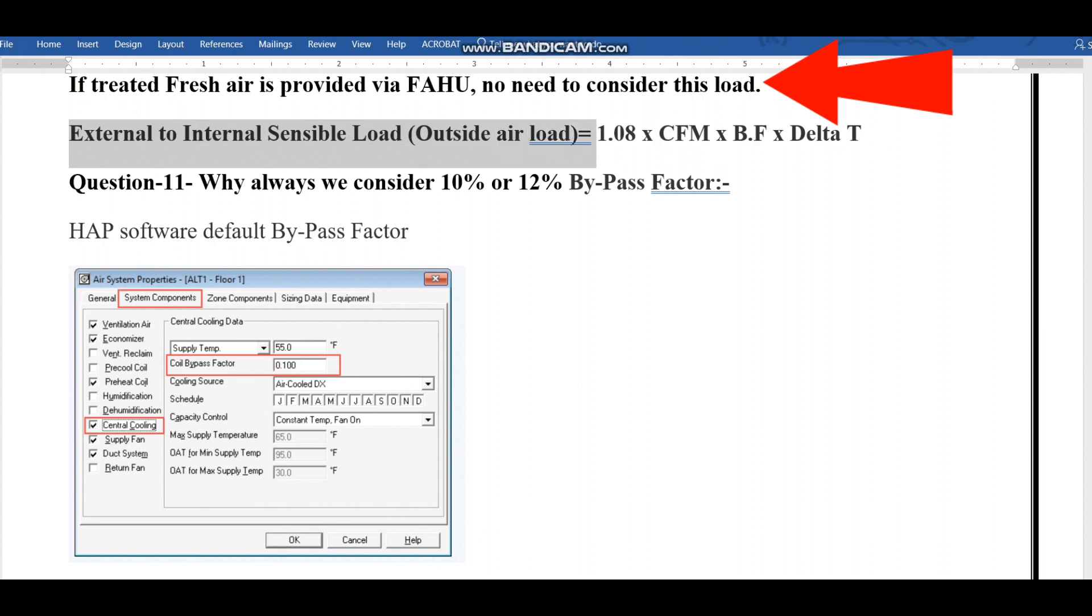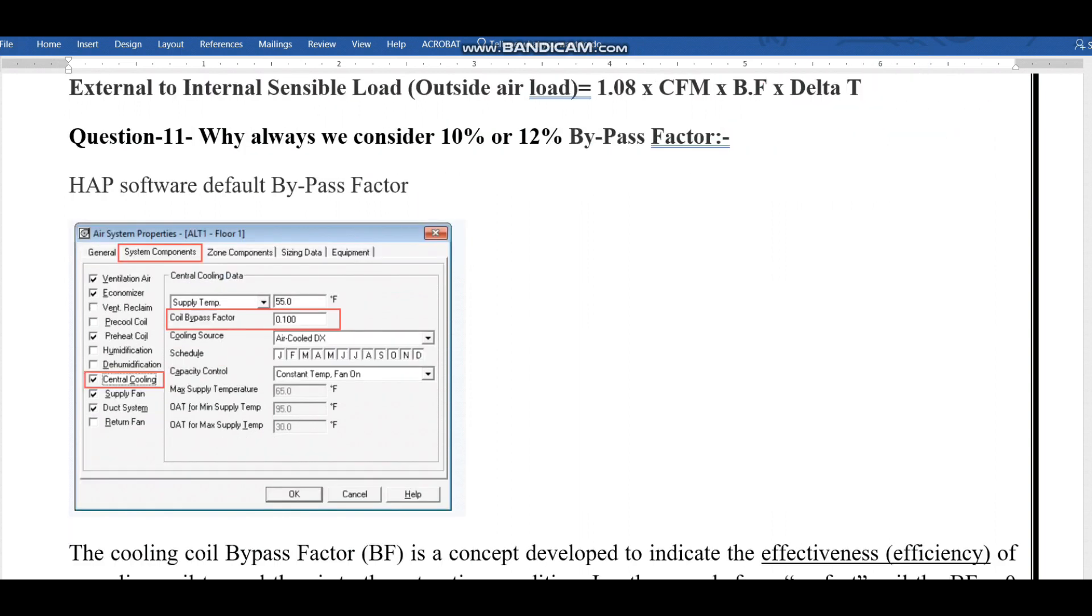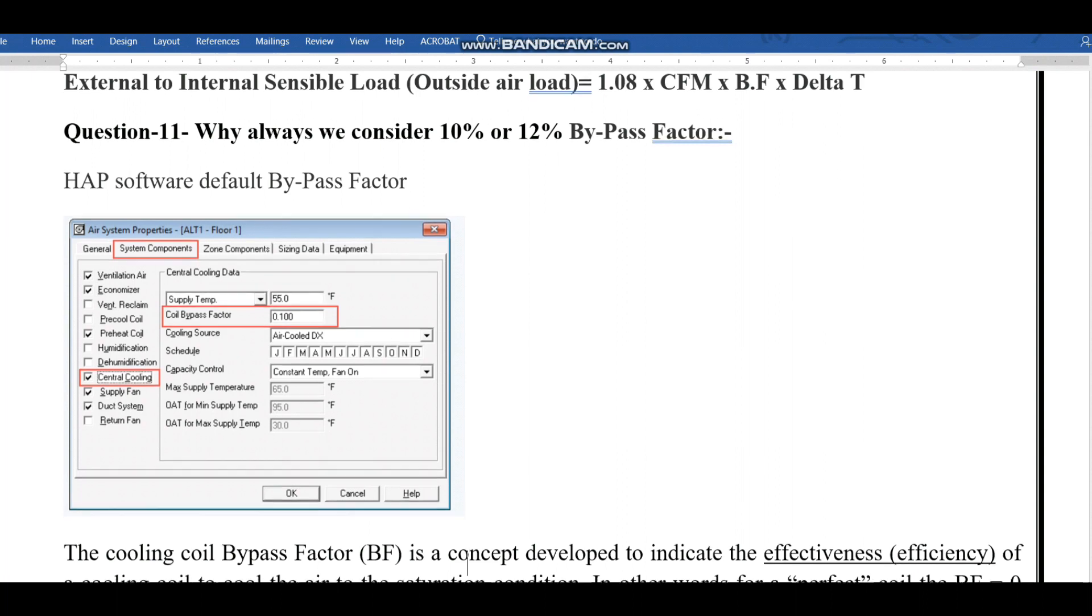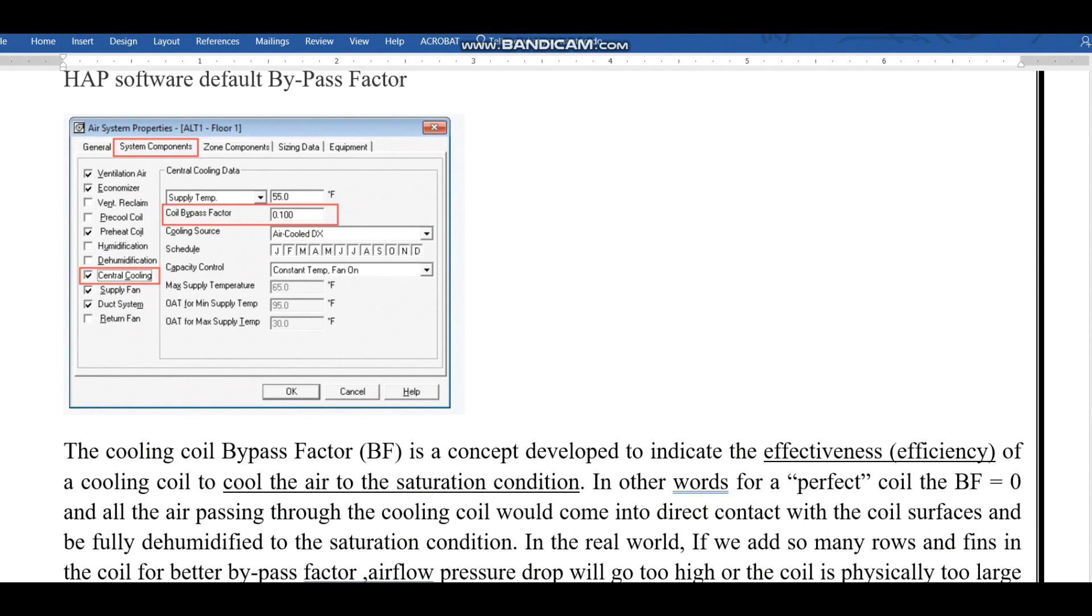Now we have the formula: external to internal sensible load, outside air load, equals 1.08 times CFM times bypass factor times delta T. If you see in the HAP software, by default the coil bypass factor will be 0.1 or 10 percent. If you pass 100 CFM air flow into the cooling coil, not all the air will get cooled, so some amount will escape. That escaped air is called bypass.